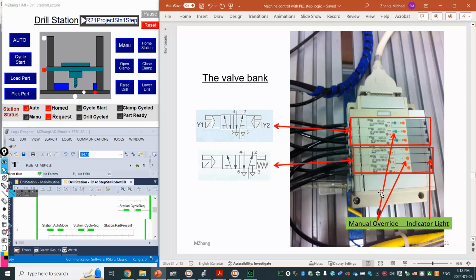All right. So on the valve bank itself, as you can see here, there are two different buttons on each valve. No, not all of them. There are two buttons on the double solenoid valve. One is green, the other one is orange. And on the single solenoid valve, you only see one button on each valve, right? So you figure that's the manual override for the solenoid. If for some reason, without an electrical signal, you want to energize the solenoid, you can use some object to push those buttons, but it's just for temporary manual override.